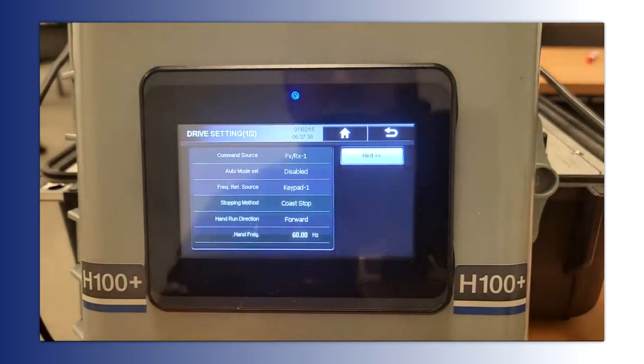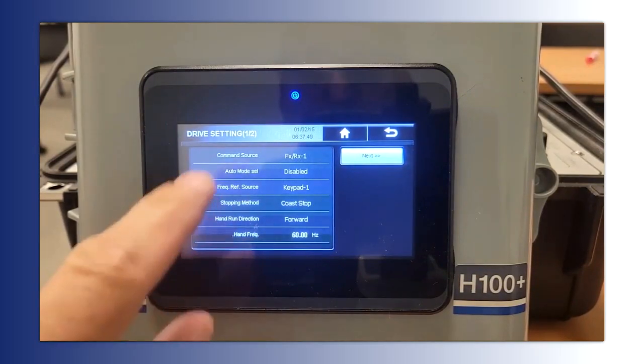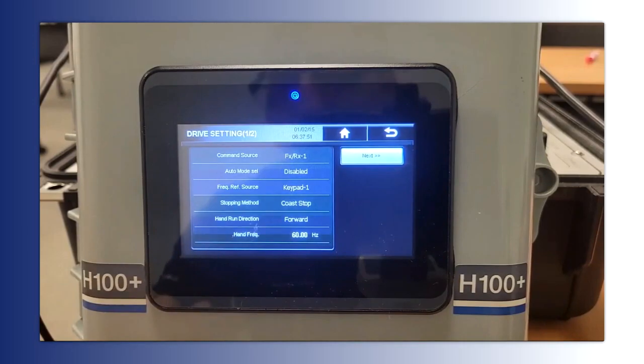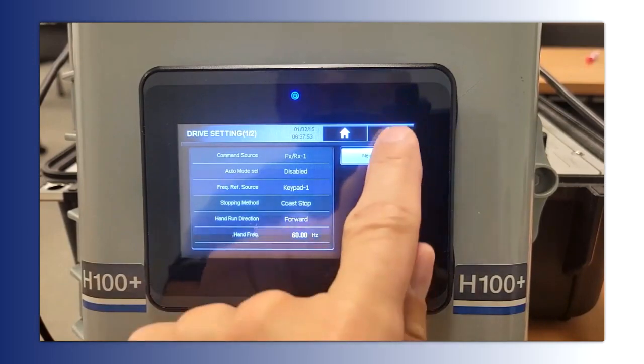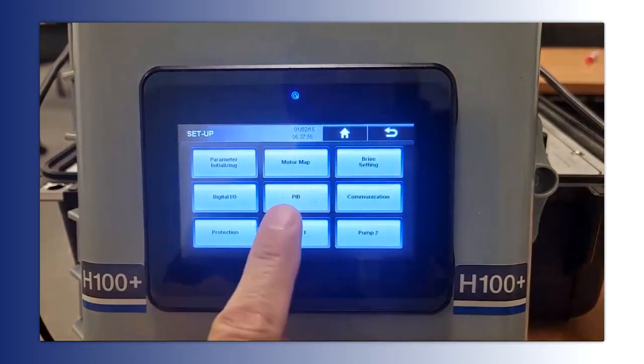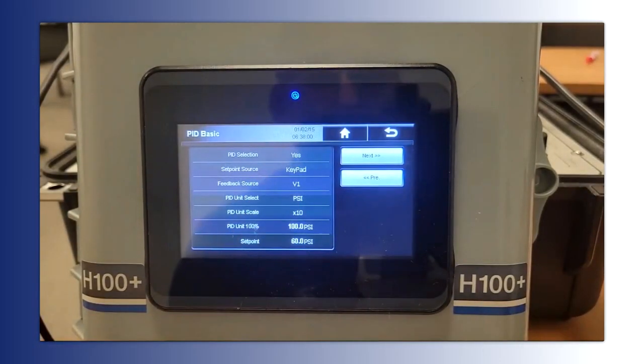So drive settings, we could see that we're running off of terminals on this. Again, we mentioned that in these slides. And auto mode key is disabled, so that means you don't need to hit the auto key. Frequency reference source doesn't matter because I'm going to show you that we're running PID. So if I go back, I can see that PID basic, PID selection is set to yes. Our set point source, commonly called PID reference, is set to keypad. So that's just like a predetermined set point, most commonly what people are doing.